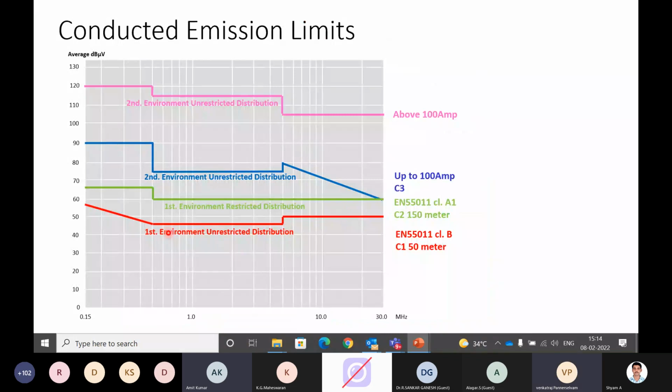This is just an example of that noise. We measure the noise level created after putting in the filters in dB. The red one is C1. You can see the noise level is very, very low, 50 to 60 dB here. The C2 filter will be somewhere around 60 to 70, and 90 for C3, and 120 for C4. So this is the difference between the four filters.